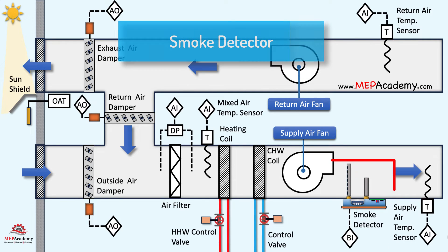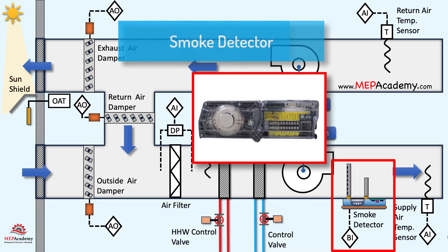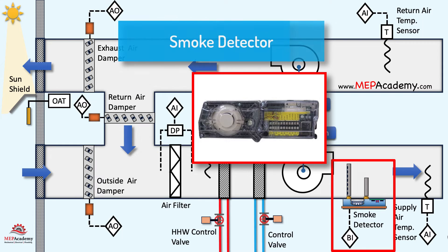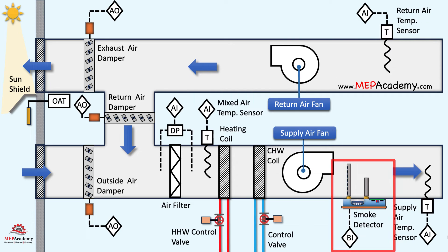The primary function of a smoke detector in an air handler is to detect the presence of smoke in the air circulating through the HVAC system. Once activated, it can initiate an automatic shutdown of the air handler to prevent the spread of smoke throughout the building. It can also trigger audible and visual alarms, alerting building occupants and personnel to the potential fire hazard.